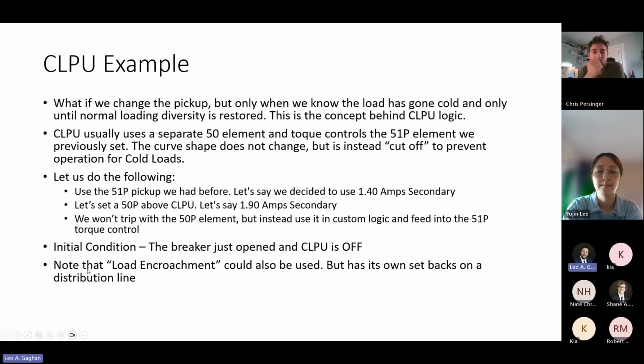Note that we could have also used load encroachment. That could have also been used, but that has some of its own drawbacks on a distribution line where there's a lot of natural imbalance. So probably haven't talked about load encroachment. If you've done settings before, you probably know what it is. It's another option that's got its own drawbacks, but it's common to use also.